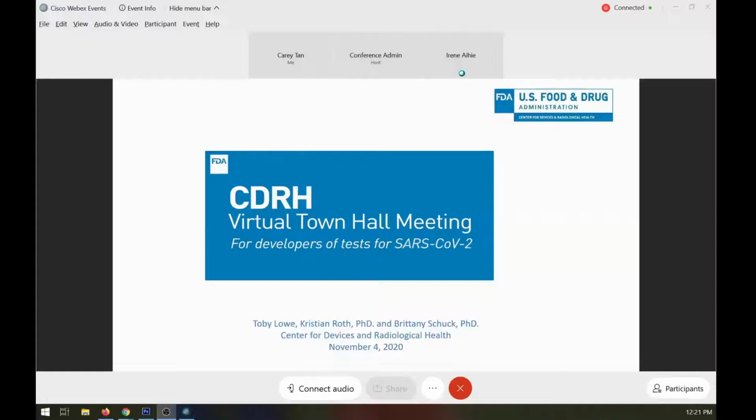Hi, Toby, Chris, and Brittany. This is Christy Bergerson from Exponent Consulting. My question is not as detailed. I had a question pertaining to research use only components that are used as part of a submission. So after the submission is authorized, do those components named in that submission, which might have been research use only before, need to change their labeling? So for example, if a company uses a certain instrument with their assay and that instrument is labeled as RUO, after authorization, would that instrument's marketing materials need to be changed to remove the RUO label?